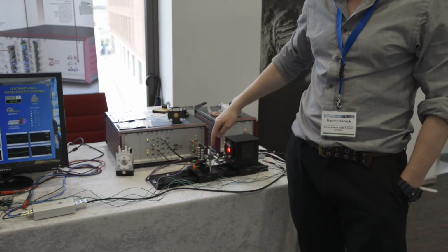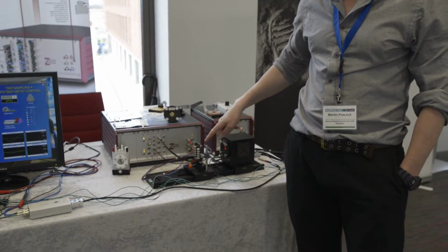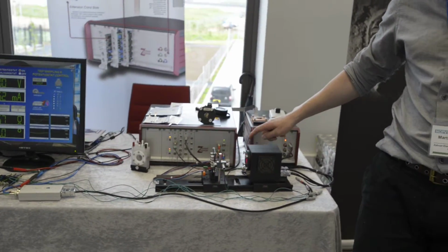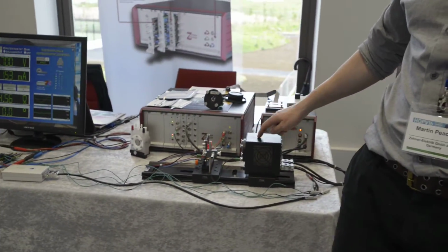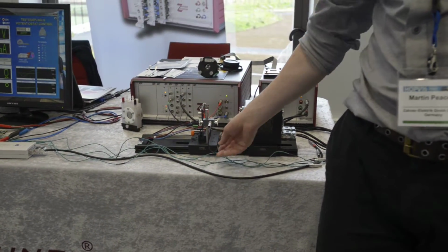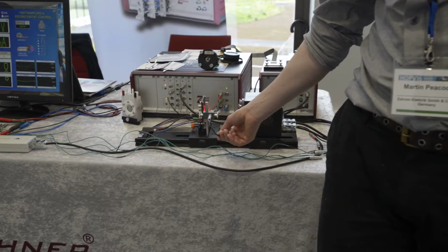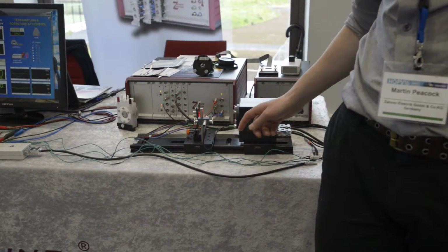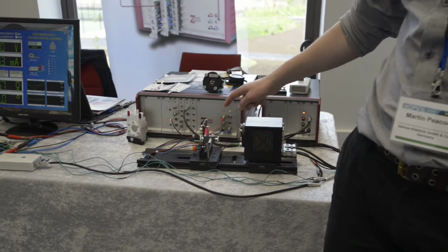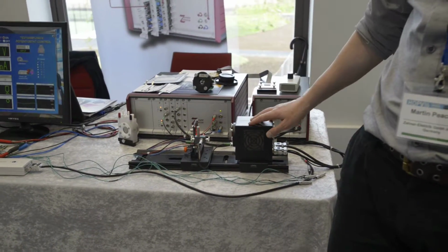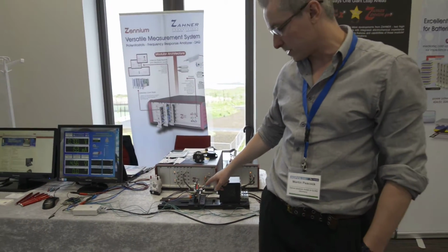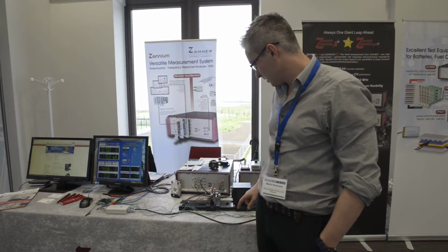What makes it slightly different is there's actually a sensor here, and that sensor is measuring the light intensity emitted by the light source. So if it's not giving the light intensity that the software is demanding, then there's a direct feedback cable here, and that allows us to increase the power to the light source so that we actually get the light intensity that we were expecting. So we did discuss photocurrent, photovoltaic, IMPS, and specifically the CIMPS with a control.